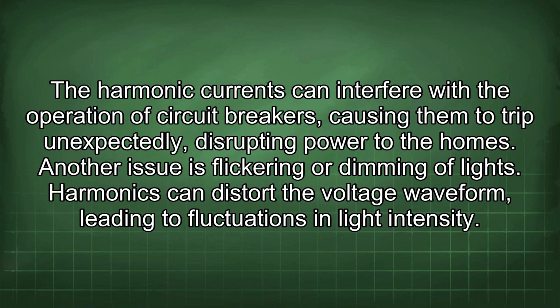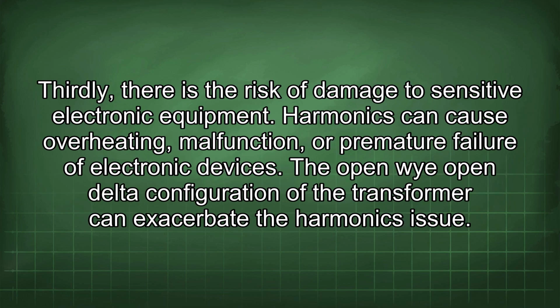homes. Another issue is flickering or dimming of lights. Harmonics can distort the voltage waveform, leading to fluctuations in light intensity. Thirdly, there is the risk of damage to sensitive electronic equipment. Harmonics can cause overheating, malfunction, or premature failure of electronic devices.